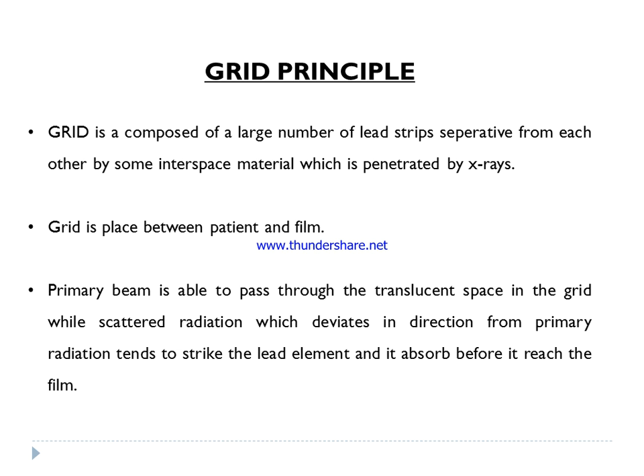A grid is mainly made up of a large number of lead strips. They are separated from each other by interspace materials which are penetrated by x-rays. A grid is placed between the patient and the film. Grid cassettes are also available in the market, and the grid can also be placed under the patient. The grid has the ability to pass the primary beam through translucent transmission spaces.